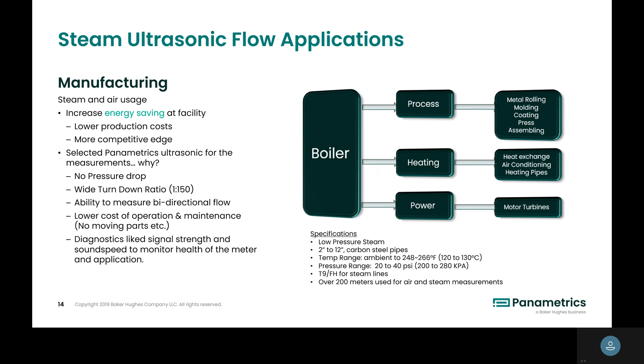From their perspective, ultrasonic flow measurement provided the rangeability they needed, with no pressure drop, bidirectional capability in certain situations, and signal strength diagnostics beyond just flow measurement that was key for them. This was mostly low pressure steam, 20 to 40 pounds of pressure, but it provided the rangeability they were looking for.